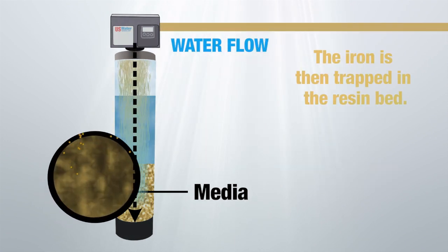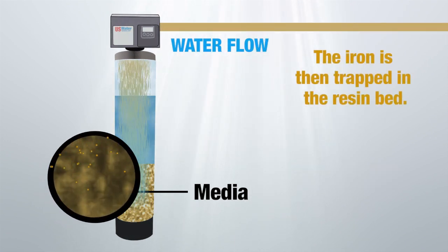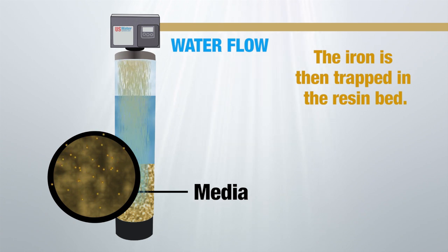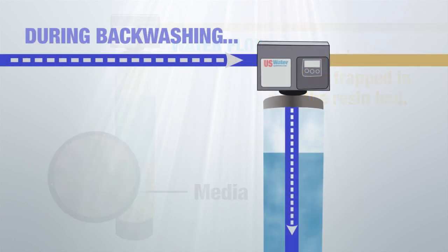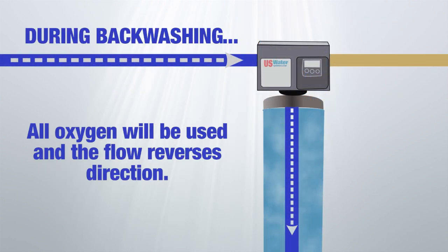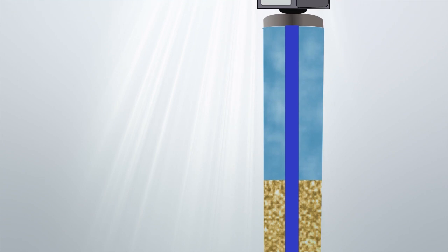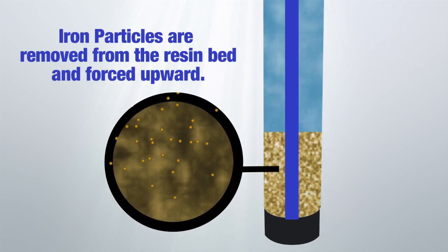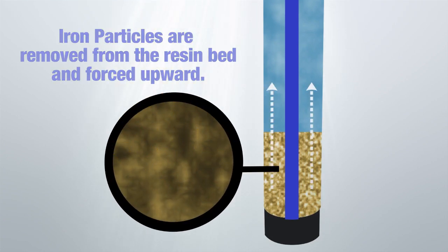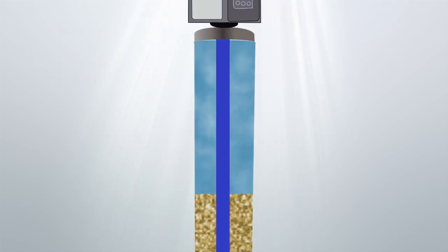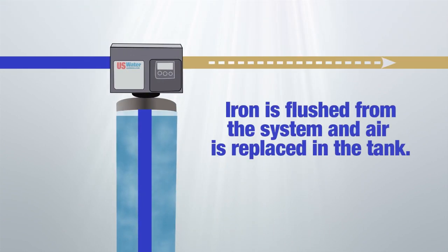But after a while of trapping contaminants, the media needs to be backwashed. That means the water flows backwards through the media down the drain, which removes the contaminants that have been collected in the media bed.